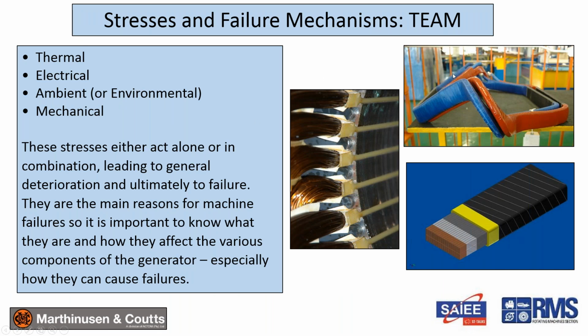Okay. So I then spoke about the difference between low voltage and high voltage. You can see a high voltage half coil is on the bottom right. Low voltage is in the center. The principles are the same. You have an overhang portion, and then you have a slot portion of the coil. You have turns, and you have main insulation.